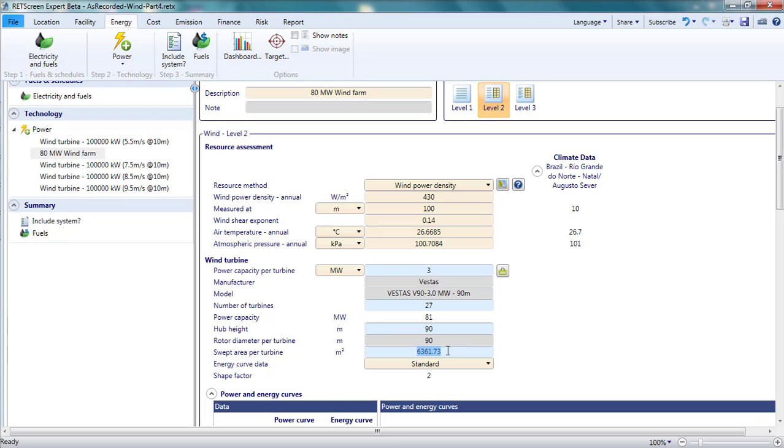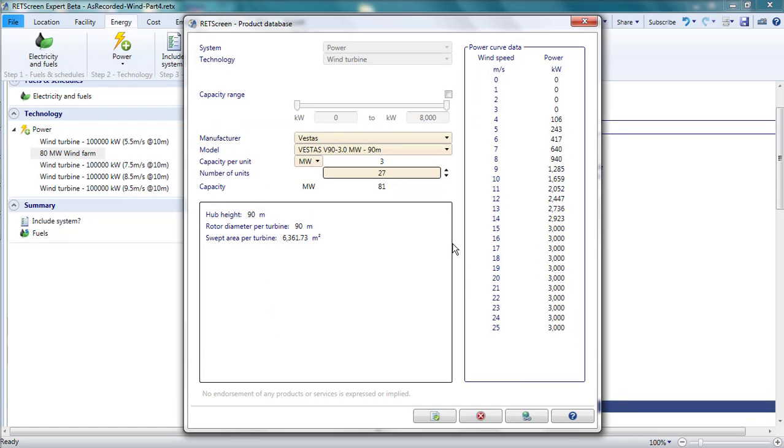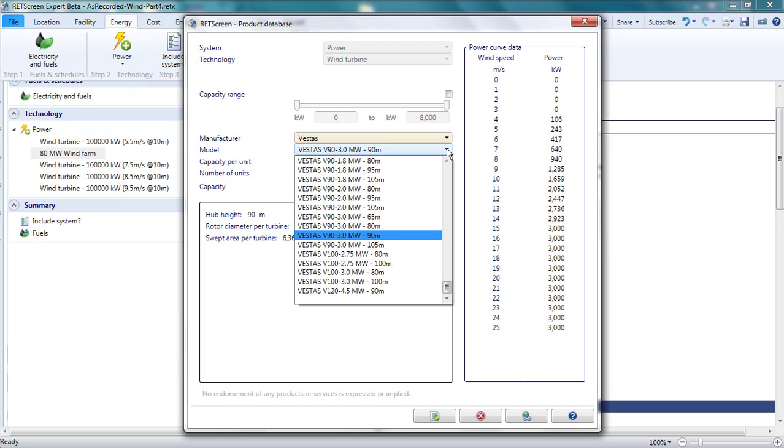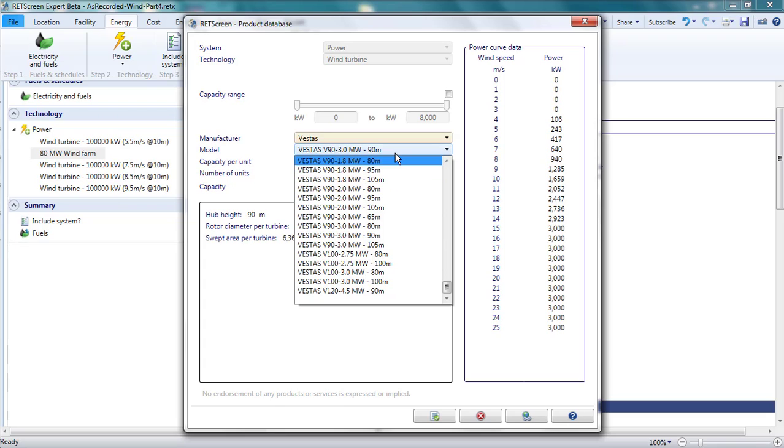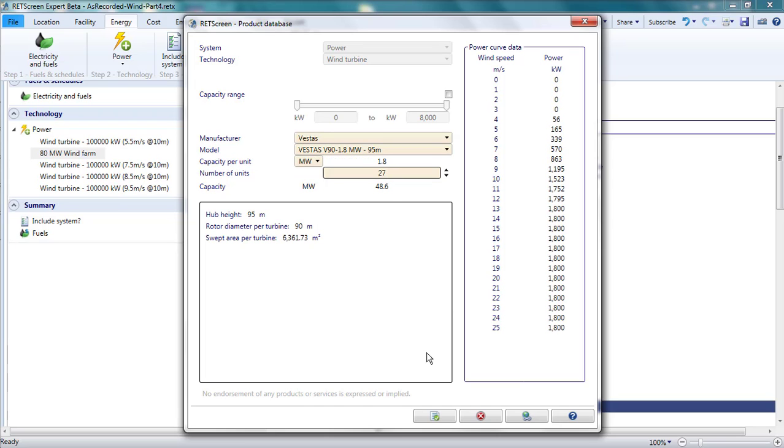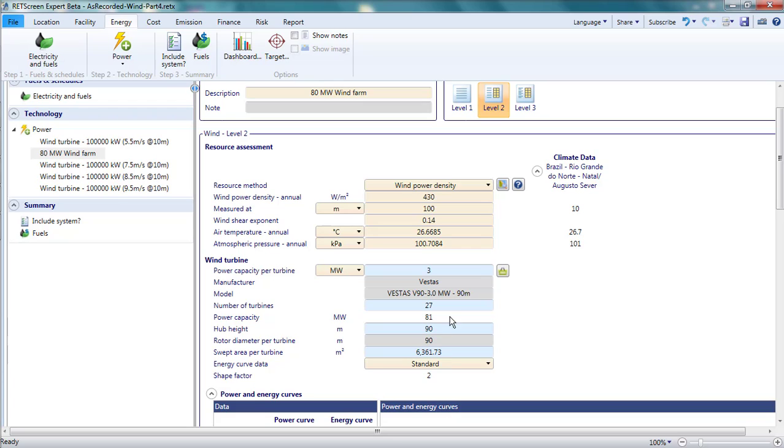In the RETScreen product database, I see that the same V90 turbine comes in a 1.8 megawatt version. It also has a 90 meter rotor. With the smaller rated power, but the same rotor size, the capacity factor should go up. I'll select the version with the 95 meter tower. It is slightly higher than the turbine we had thus far, so to compare apples with apples, I'll overwrite the hub height with 90 meters.